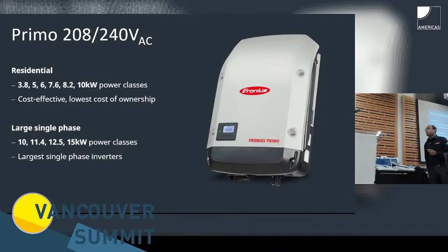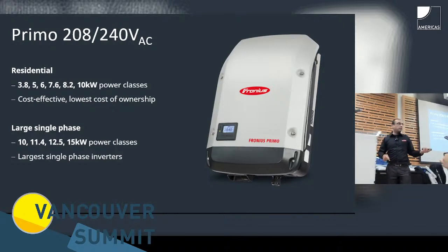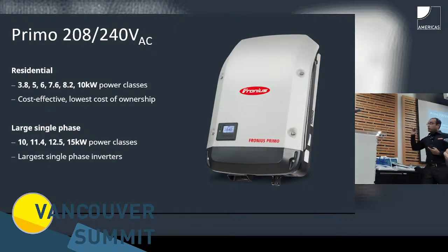You also have to remember that the inverter is the only smart component of the system that can complain if anything goes wrong. But oftentimes, it's assumed that if the inverter complains, the problem is with the inverter, not elsewhere. So within those first 2 or 3 years, as long as the inverter isn't already damaged, we're usually able to find the cause of those problems and get them fixed so you'll have fewer such issues going forward.